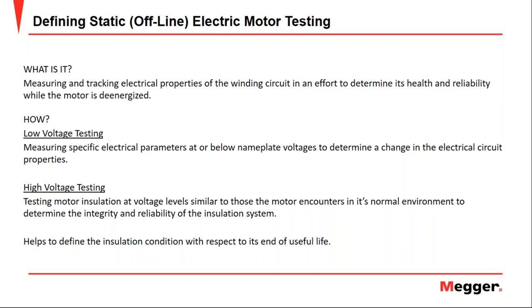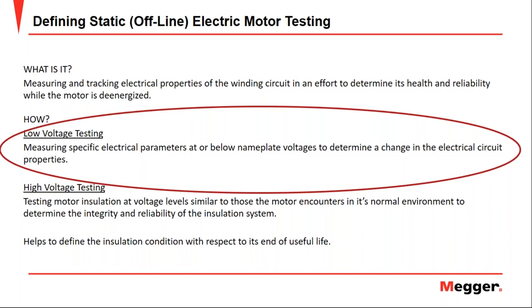But if a fault is detected by carrying out the test from the MCC, the problem could be either in the motor or in the power cable insulation. So we have to be very sure about the fault location and how it's going to affect the whole system. The static tests are divided in two groups, the low voltage tests and the high voltage tests. In this webinar, we're going to see the low voltage tests in detail. These tests are performed at or below the bus voltage, never above that level. However, in order to have an effective diagnosis of the insulation system, both must be performed. Low voltage tests are pass or fail tests, but the high voltage tests give predictive indication and allow me to have a clearer scenario of the motor insulation condition, as we will see a little later.